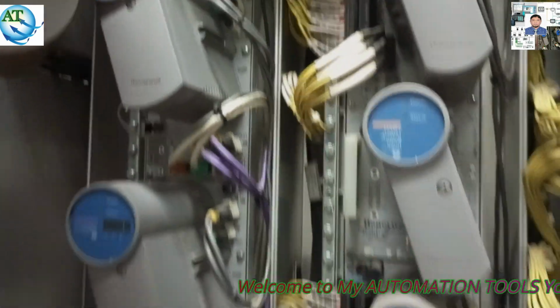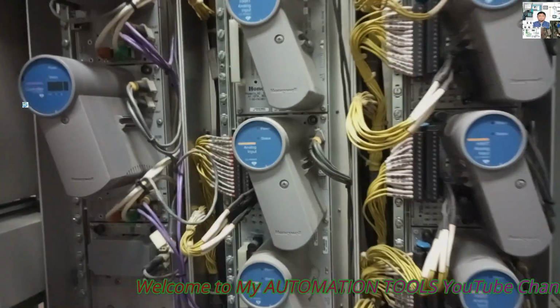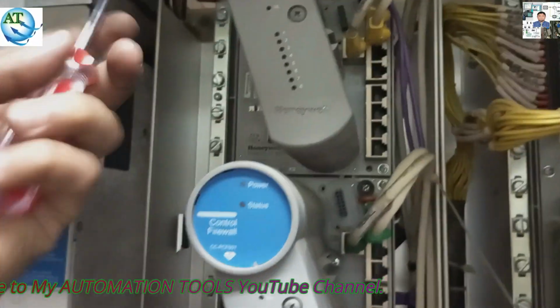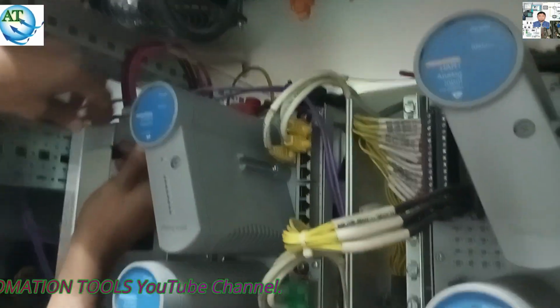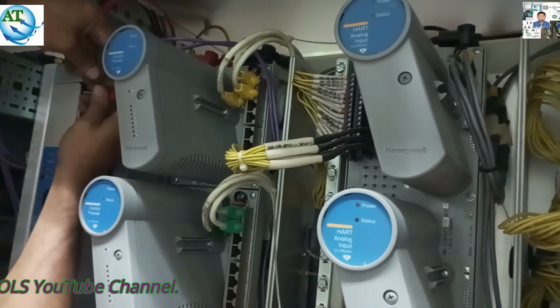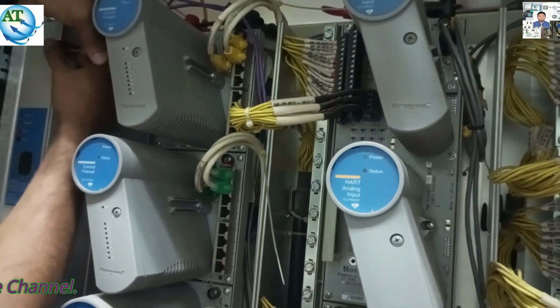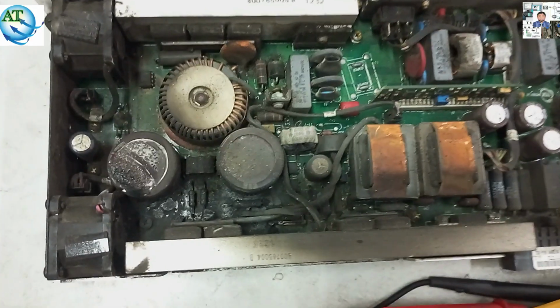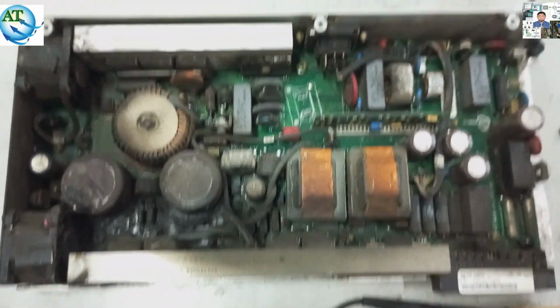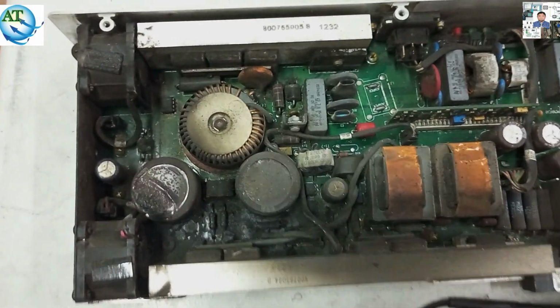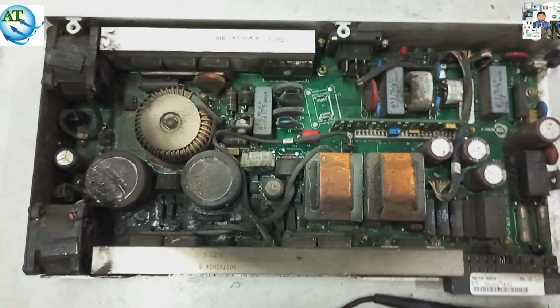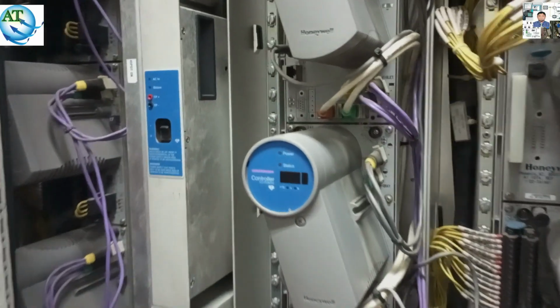Suddenly both power supply units, the redundant power supply units, burned. For that reason the controller goes to the stop mode, and our plant is shut down. Both power supply units have been damaged and burned. For that, the controller does not get power, and it goes to the stop mode.